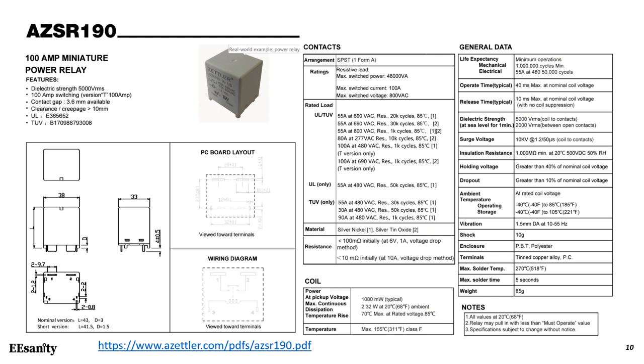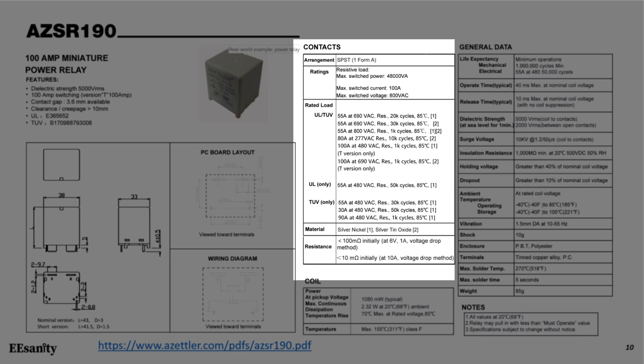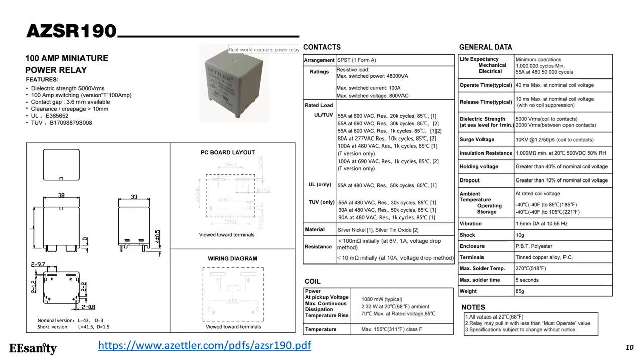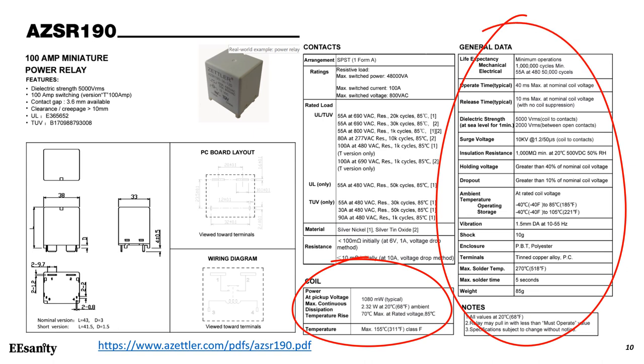This is another example showing a power relay, with important parameters copied from the datasheet. This is a 100-amp relay for DC and AC applications. The AC contacts can operate at up to 100 amps and 480-volt AC RMS voltage. You can see the general data and the coil data for this kind of relay.